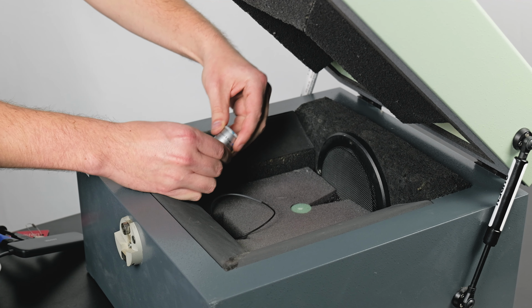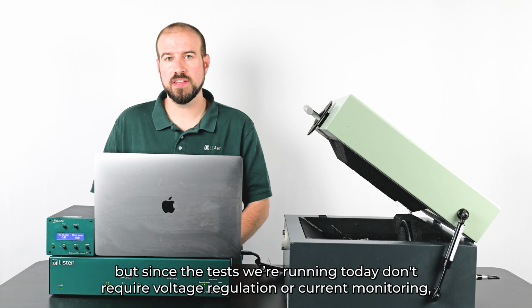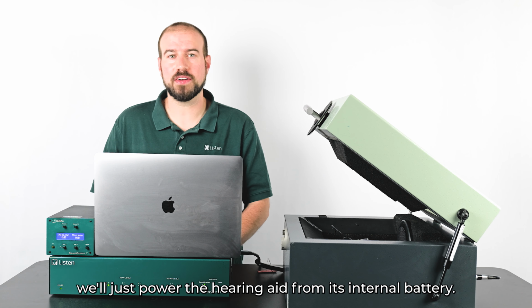We also have an SEM reference free field microphone, which is also going in the test box. The 1/2-inch mic needs LEMO power, so it's connected to a SoundConnect 2 power supply, and the mic input then goes into the AmpConnect 621 audio interface. The AmpConnect also provides power for the SEM mic and amplification for the speaker in the test box. If I were running the complete suite of ANSI S3.22 tests, I would also need a DC power supply and current monitor, but since the tests we're running today don't require voltage regulation or current monitoring, we'll just power the hearing aid from its internal battery.